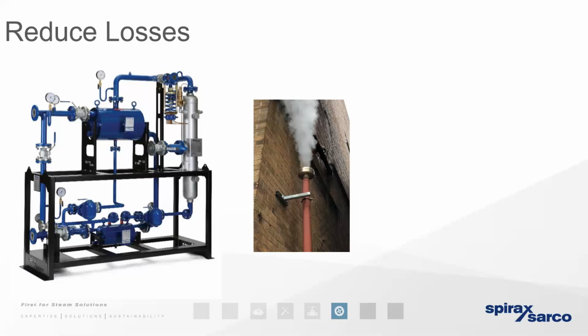And it can add that heat energy. So we're adding both the latent heat energy that's present in the flash and the sensible heat energy in the condensate to another process, to another heat sink. Now, even if we don't have another heat sink available locally to the process, wherever that pressure drop is taking place, wherever that flash steam is being produced, if we can get it back to the pressurized deaerator, or even if we don't have a pressurized deaerator, if we can get it back to that thermal store that we've spoken about, then we can use this flash steam to charge the vessel.